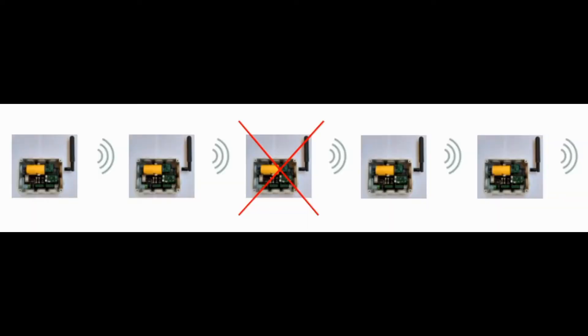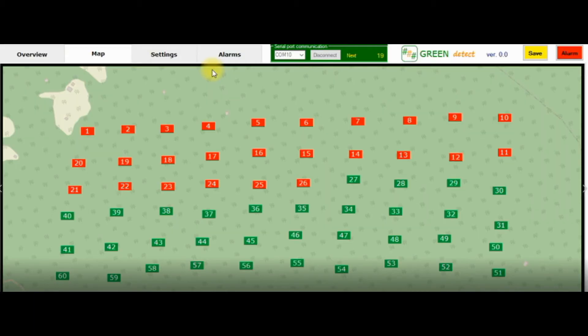In the event of a module failure, communication is interrupted and the acquisition of all sensors is momentarily lost. After a delay time of 2 minutes, the module following the faulty one begins to transmit data to the following modules, informing the supervisory system of the fault. This condition generates a specific alarm, and it is therefore possible to go promptly to replace or repair the faulty module and restore the network in a very short time.